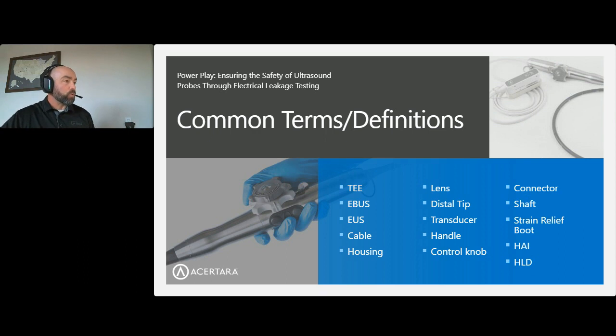The housing of a probe, depending on the probe that you're talking about, typically surrounds the actual ultrasound array itself. It has a lens set in it, and that's true for TEE probes. It's also true for standard, what I would call G&E probes, or general and endocavity probes. The ultrasound array is definitely the most sensitive part of the transducer. So it's something that you want to be very cognizant of when you're doing the electrical leakage testing, and when you're doing any sort of cleaning of the probe. That's the area that's most likely to be damaged during those processes. So you want to make sure that you've cared for it, it has been inspected, and there's not going to be obvious failures to come out of that before it goes into those harsh, high-level disinfecting steps.